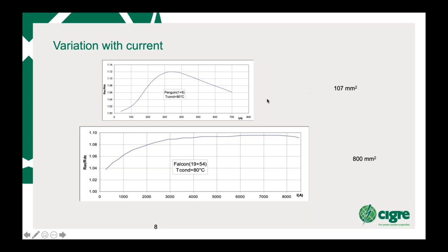You can actually look at the current down the conductor as a function of the AC to DC resistance ratio. So in other words, if there was no AC resistance increase due to current, that would be one. The resistance here, you can see, goes up to around 12%. Why it goes down again is because the steel core is saturated. Now, that's a single core conductor. So when you're looking at very high current densities on MV lines or lines with Hare conductor, for example, you need to be careful of your volt drops when you are running at around 3 amps per square mm.